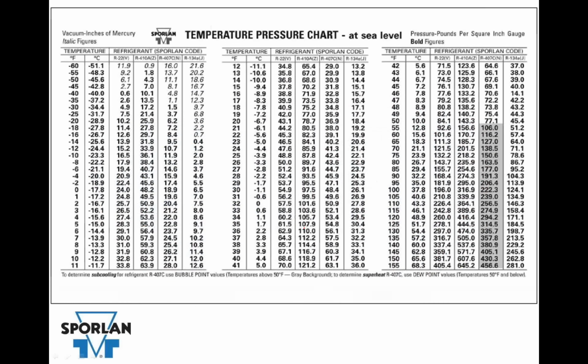Now, before we hit that, I threw this slide in here because I also wanted to show you a couple things, because obviously at the end of the day, the only reason we measure pressure is to convert to a temperature, and we're converting to a temperature so we can calculate superheat and subcooling. So if you look at these temperature pressure charts that are out, almost all of them are exactly like this. And you can see here, if we're looking at this section of the chart right here, it goes up in 1 degree increments, right? So 30, 31, 32, 33, through 40. That's pretty normal. And it's showing you over here the corresponding pressure for that saturation temperature. And so we're dealing with 1 degree increments.